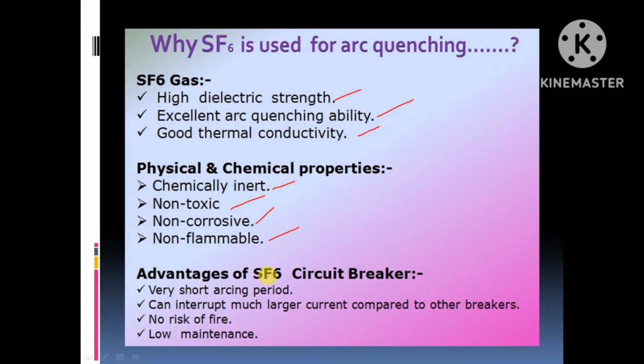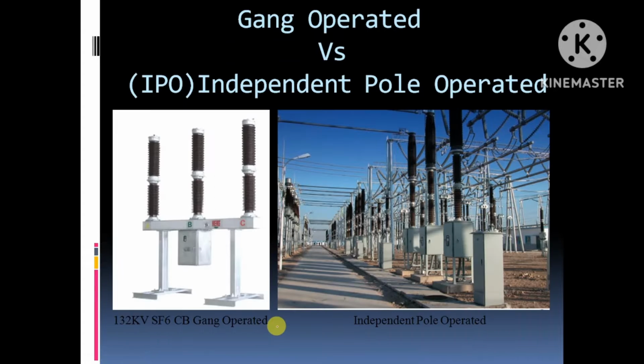And why are we using SF6 circuit breakers? The advantages are a very short arcing period, it can interrupt much larger current compared to the other breakers, there are no risks of fire, and very low maintenance is required. So these are the advantages of SF6 circuit breakers.